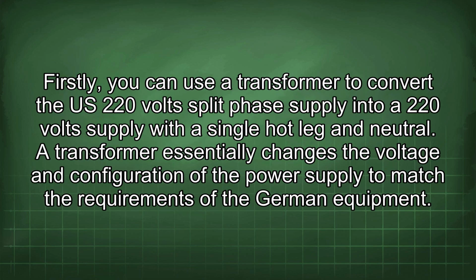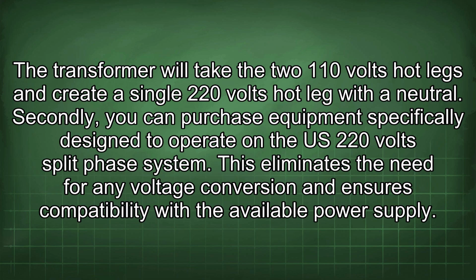Firstly, you can use a transformer to convert the US 220 volt split phase supply into a 220 volt supply with a single hot leg and neutral. A transformer essentially changes the voltage and configuration of the power supply to match the requirements of the German equipment. The transformer will take the two 110 volt hot legs and create a single 220 volt hot leg with a neutral. Secondly, you can purchase equipment specifically designed to operate on the US 220 volt split-phase system. This eliminates the need for any voltage conversion and ensures compatibility with the available power supply.